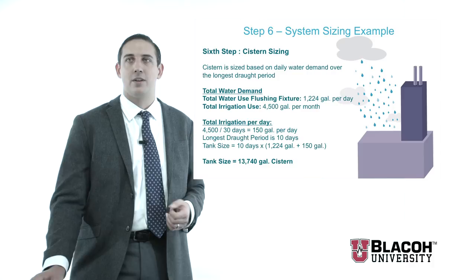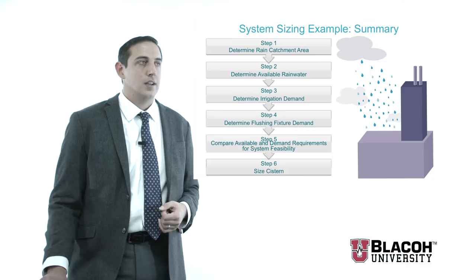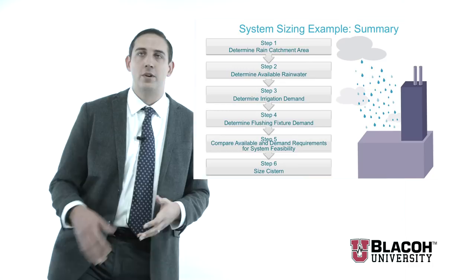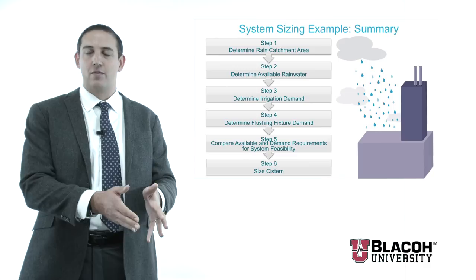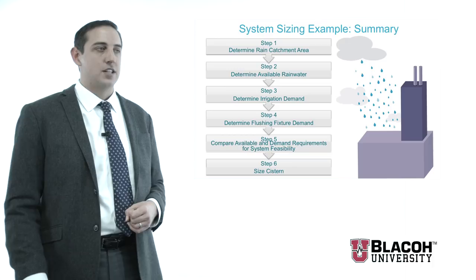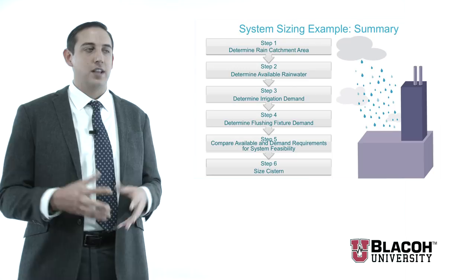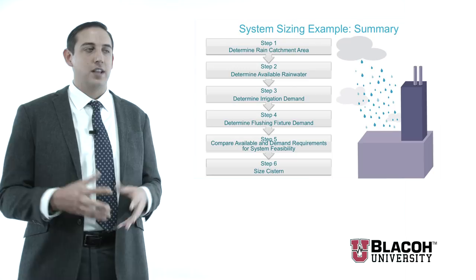To summarize this section: your first step in system sizing is to determine your rain catchment area. Your second step is to determine your available rainwater using: monthly rainfall × loss factor × runoff coefficient × catchment area. The next step is to determine your irrigation demand if applicable, then your flushing fixture demand or other uses such as cooling towers. Compare available and demand requirements for system feasibility — targeting 50% or better on average — and then size your cistern accordingly.